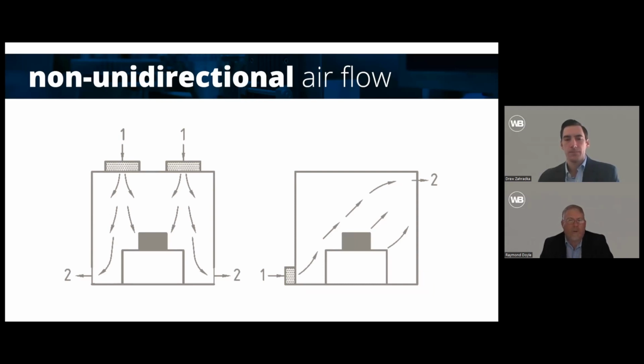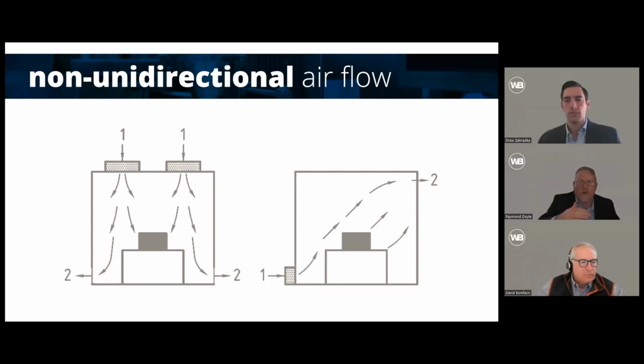A lot of times people misuse this term in the case of science because they like to call it a unidirectional flow, but it's not a true unidirectional flow. It's a unidirectional flow at the top of the room and maybe down to a certain profile in the room, but then it becomes turbulent at the lower levels before it draws out the low returns. So it's important when we talk about these things that we use the terms correctly. Same thing on the right: when you feed from the bottom and feed to the top, you can get a good flow from left to right, but there's a little more turbulence across the occupied space or the equipment within the space.